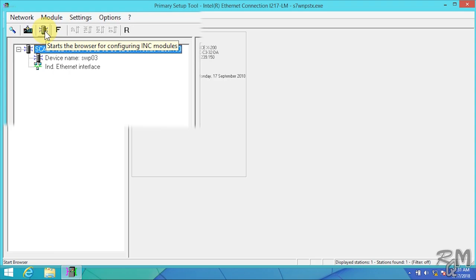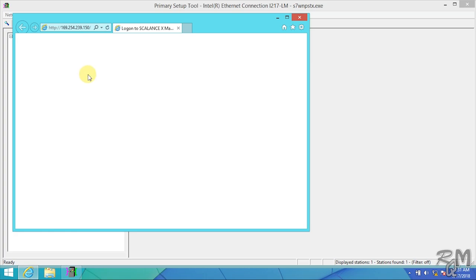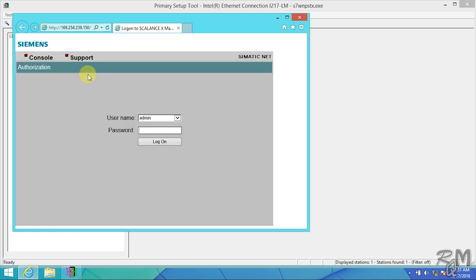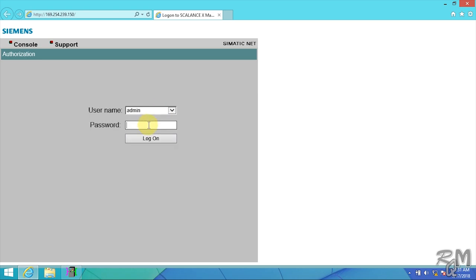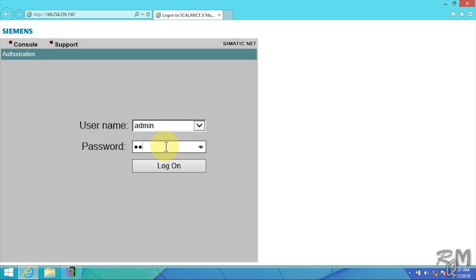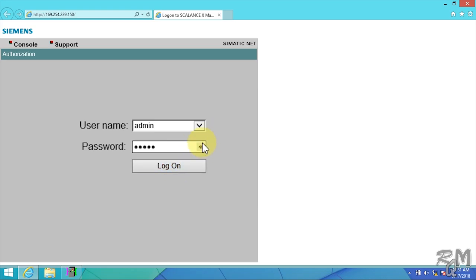SCALANCE switch web-based management page will open. You need username and password to access configuration parameters. By default there are two types of usernames. One is 'user' and its password is also 'user' - it is only to read the configuration of switch. Second is 'admin' and its password is also 'admin' - it is used to read and write the configuration of SCALANCE switch. I will enter username admin and password admin as you can see by click on i button. Click on login button.